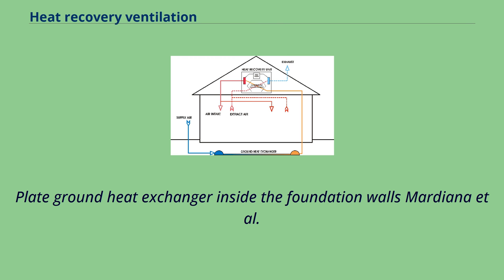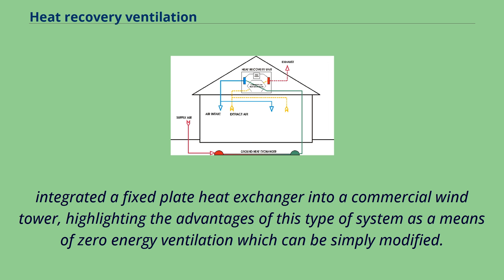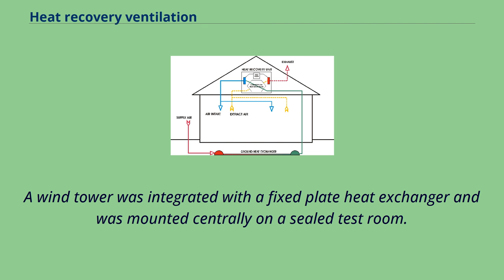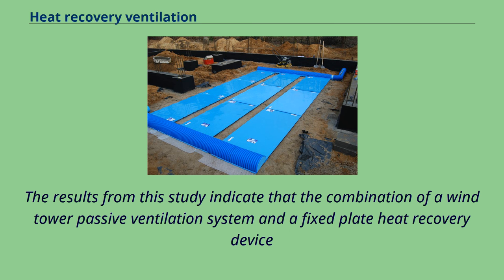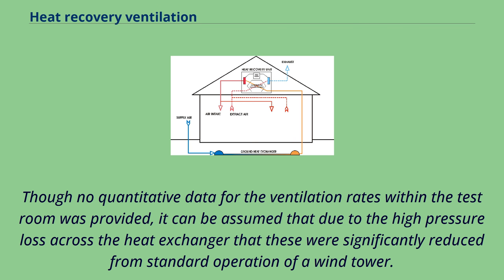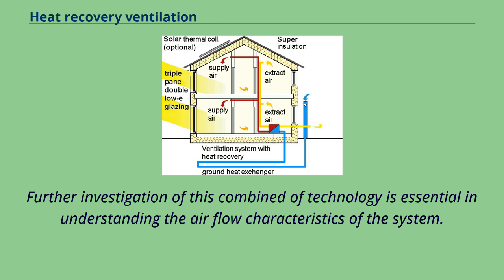Mardiana et al. integrated a fixed plate heat exchanger into a commercial wind tower, highlighting the advantages of this system as a means of zero-energy ventilation which can be simply modified. Full-scale laboratory testing was undertaken to determine the effects and efficiency of the combined system. Results indicate that the combination of a wind tower passive ventilation system and a fixed plate heat recovery device could effectively recover waste heat from exhaust air and cool incoming warm air with zero energy demand. However, due to the high pressure loss across the heat exchanger, ventilation rates within the test room were likely significantly reduced from standard wind tower operation.